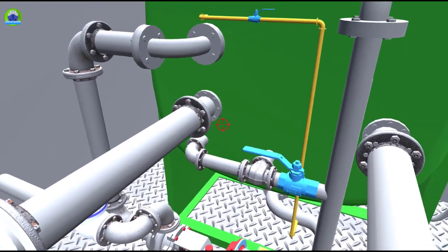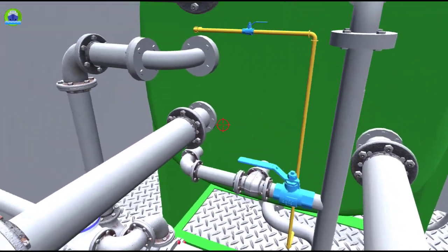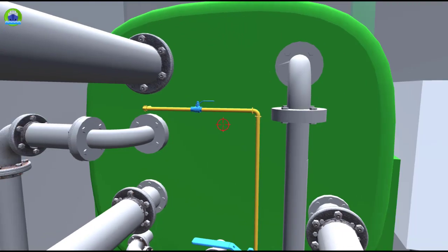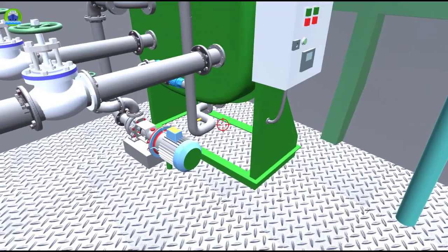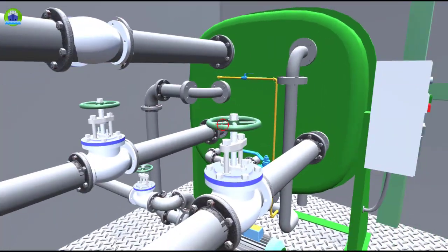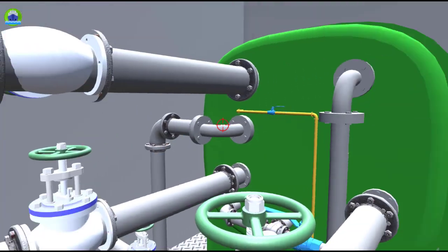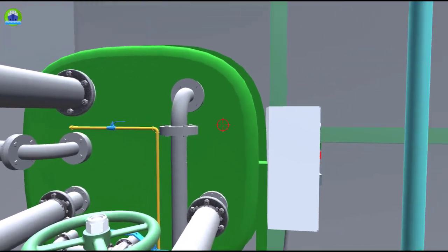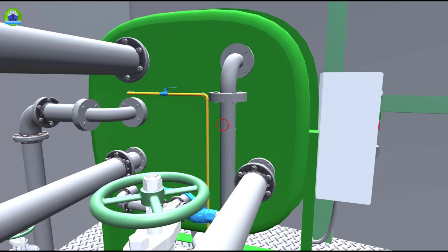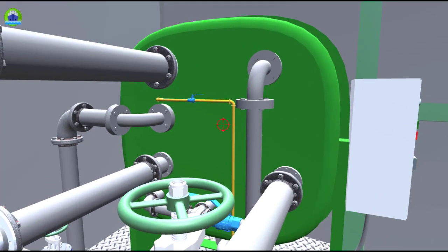So what happens now is that the seawater inside that has been bled out proportionally by this pipe will be evaporated from within. Now, this yellow line, if we can represent it, is actually connected to the eductor. That eductor will apply the so-called Venturi effect, wherein it sucks air and liquid and creates vacuum within the chamber. And thereby, if there is a negative pressure or vacuum, of course, the boiling point of water will be lower. Hence, just at about 50 degrees Celsius, the water boils and turns into a vapor or mist.